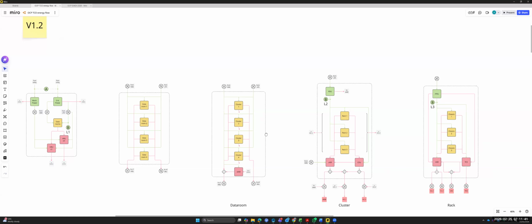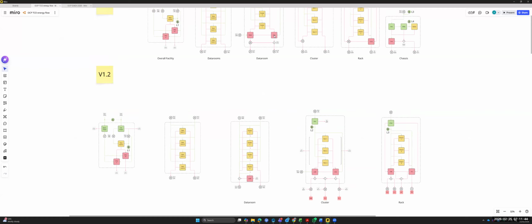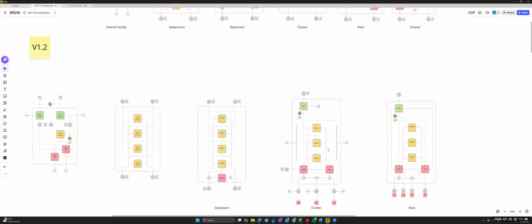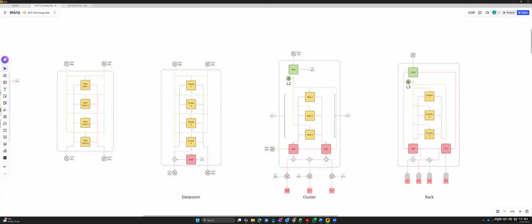But also, and more importantly, the liquid cooling, which was a CDU at the data room level, is now placed at the cluster level. We also have a block for distinction between facility water, low and high temperature cooling, but also technology water cooling equipment at the rack level. This enables us to more fully and transparently represent the efficiencies of power and cost of those objects in the stack of equipment.